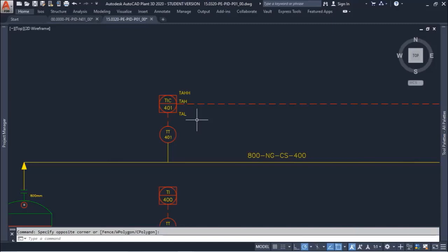if we reach 60 degrees Celsius, the TAHH will alarm and shut down the system. This means we will isolate the source of the disturbance and stop equipment to prevent safety issues.